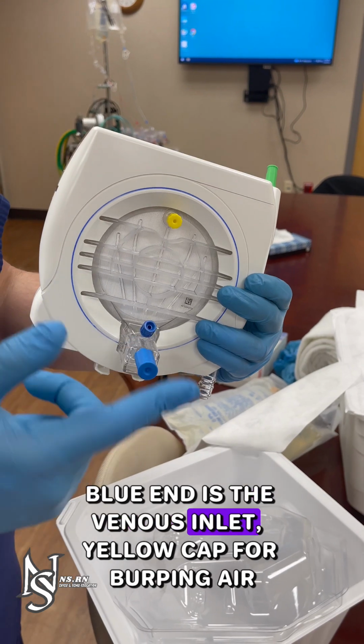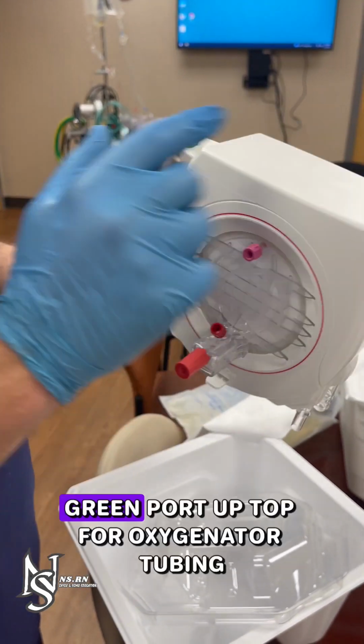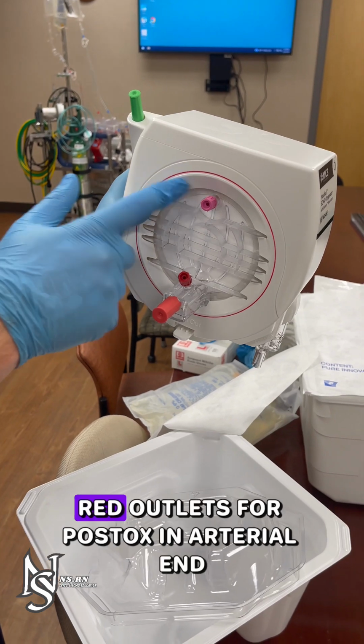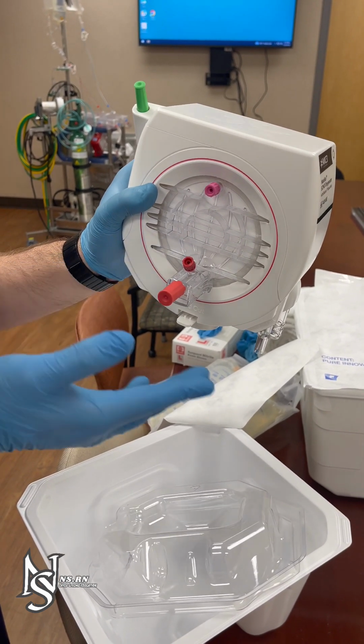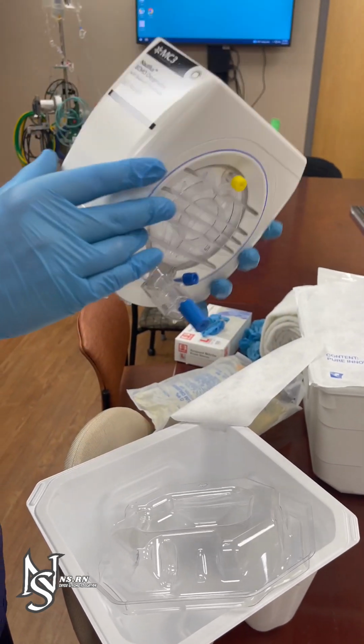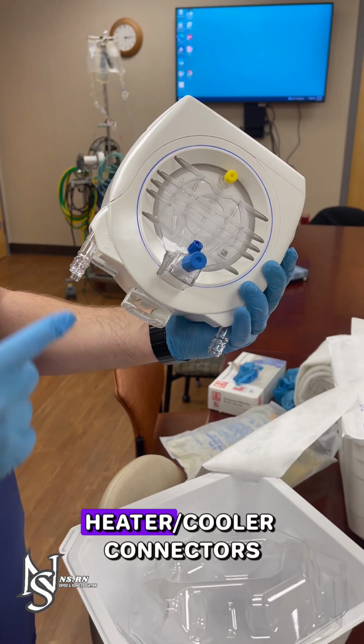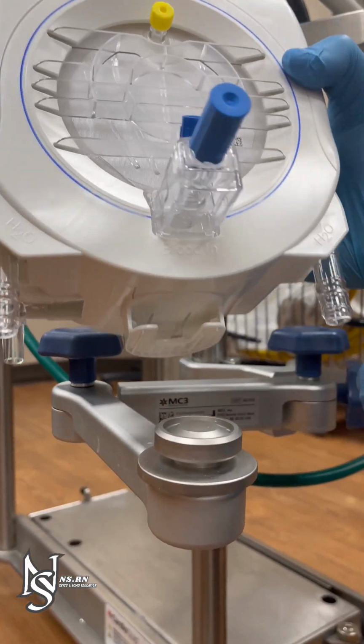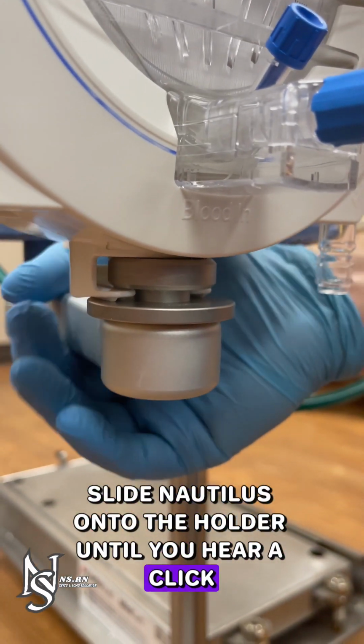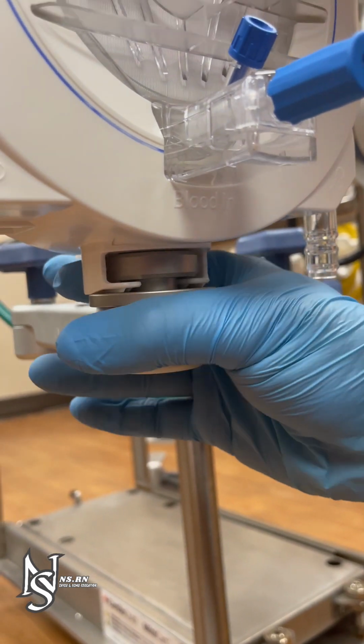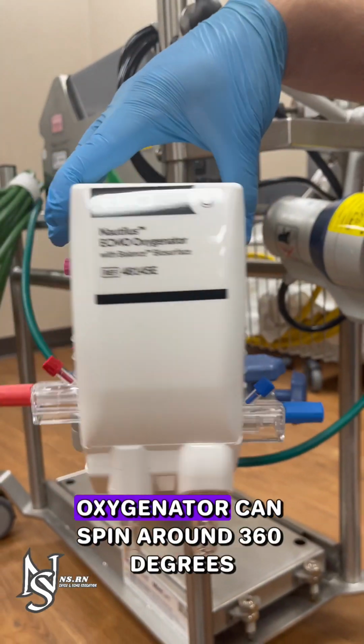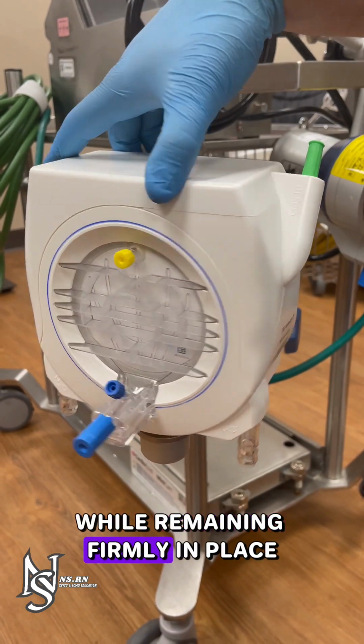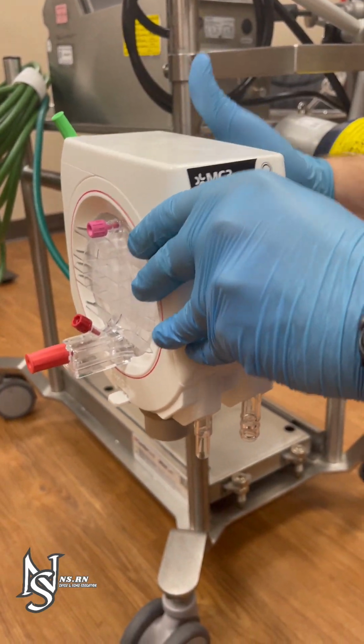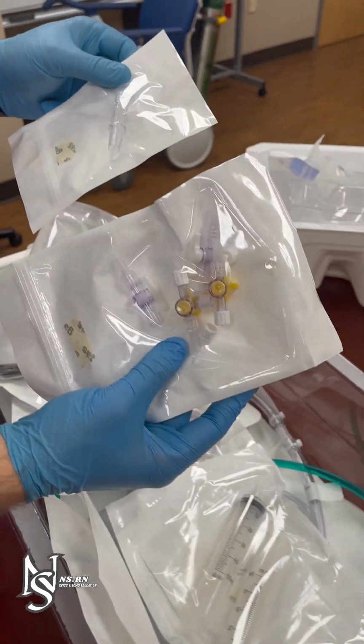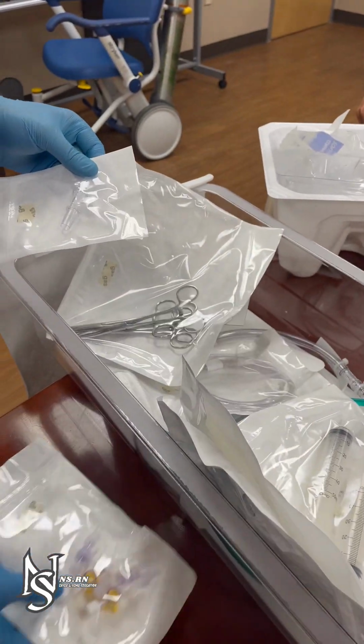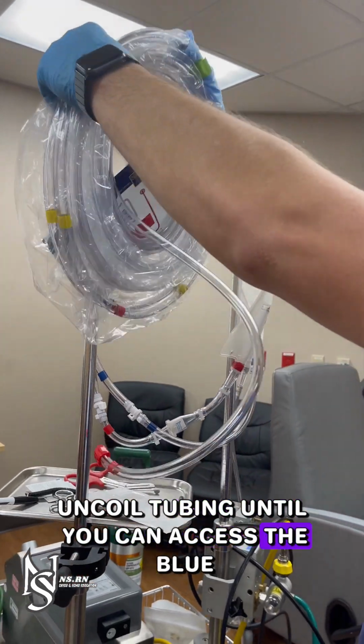Blue end is the venous inlet, yellow cap for burping air, green port up top for oxygenator tubing, red outlets for post-ox and arterial end, heater/cooler connectors. Slide Nautilus onto holder until you hear a click. Oxygenator can spin around 360 degrees while remaining firmly in place. Uncoil tubing until you can access the blue and red ends easily.